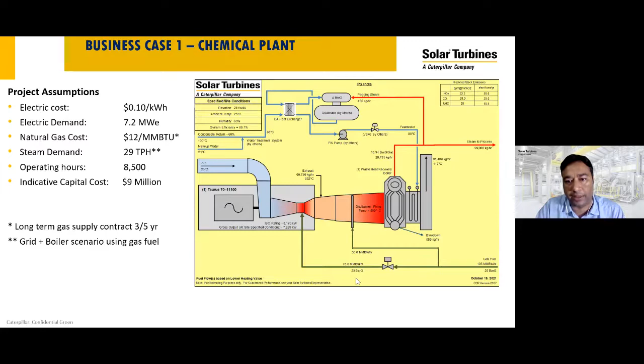You can see the heat mass balance diagram where the gas turbine is utilizing the gas available at 23 bar to burn in the combustor of the gas turbine. The exhaust of the gas turbine carries a lot of energy: 90,000 kg per hour of exhaust flow at 532 degrees centigrade. To reach 29 TPH of steam generation, we will need to do some duct firing.